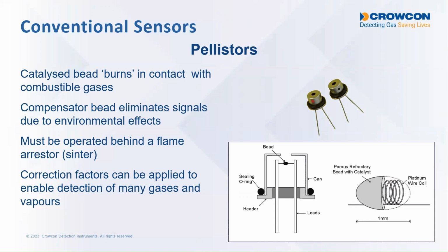Because it's very, very hot, we need to operate it behind a flame arrestor, we call it a sinter, which can present some challenges of getting gas in and out of the sensor, but it will respond to many different gases and vapors. So it will respond to methane, hydrogen, butane, propane in a linear way, so we can calibrate with methane gas and apply correction factors for other gases, but it would only be accurate for methane or the gas that it's been corrected for. If it sees any other type of gas, then it will respond, but the LEL gas concentration reading won't be accurate.